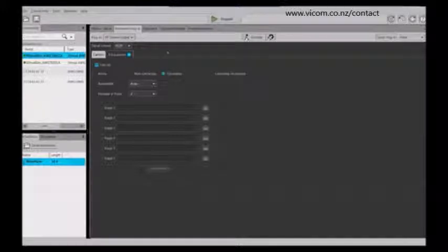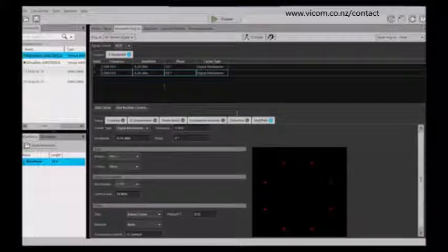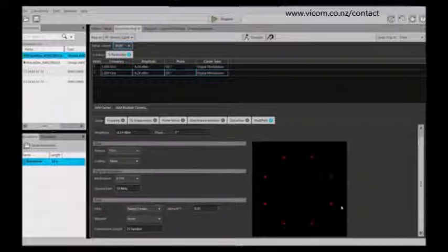In short, that's basically the characteristics of our RF generation tool. So it's fairly straightforward. Again, you can do RF or IQ type waveforms. You basically set up the characteristics of the waveform that you want to use, depending on how many carriers you want to create. You can then compile it and then just send that to the AWG, and you're off and running. So this again is a very, very useful tool, and I think that anybody doing any RF applications will find this tool very easy to use and very functional for a lot of their applications.